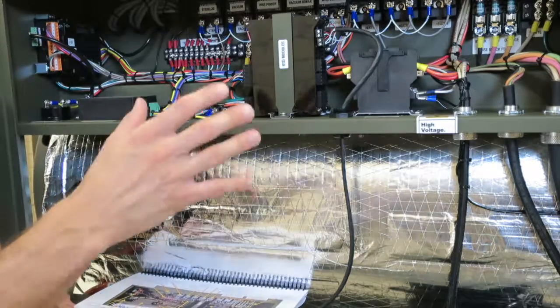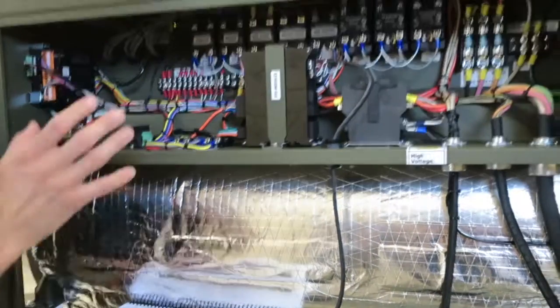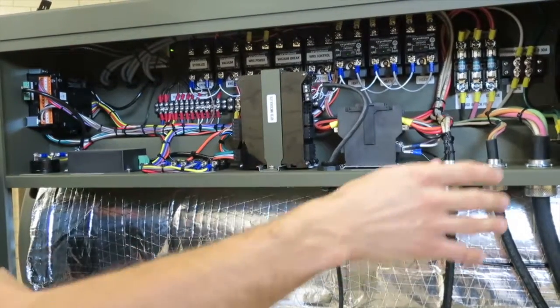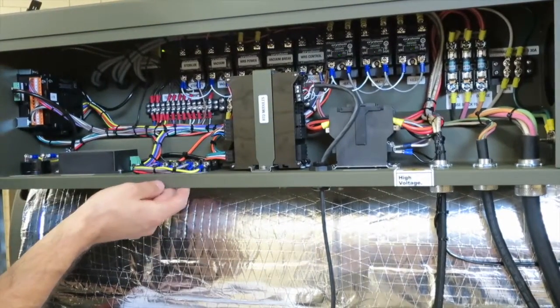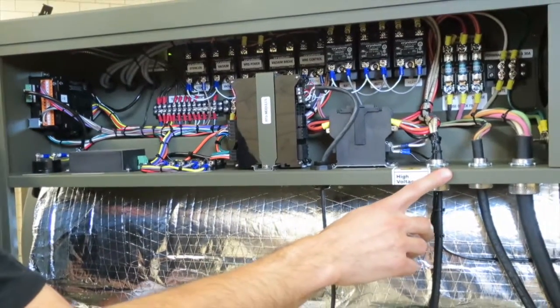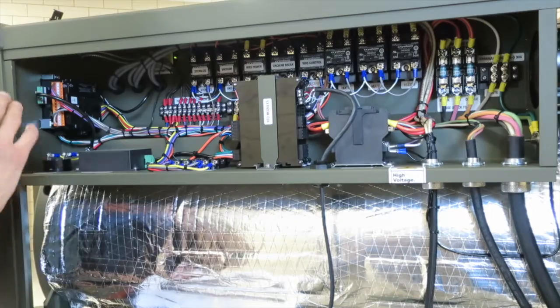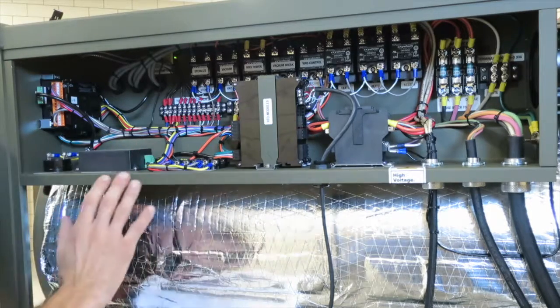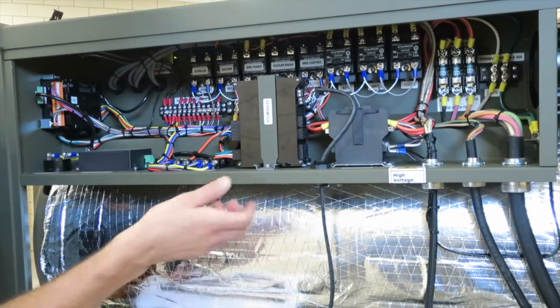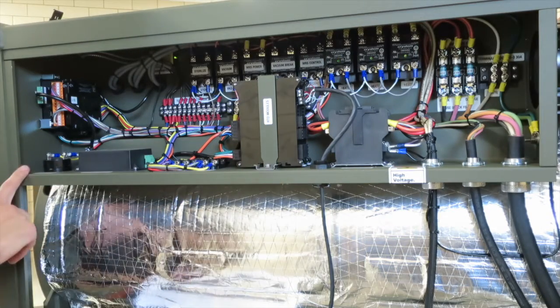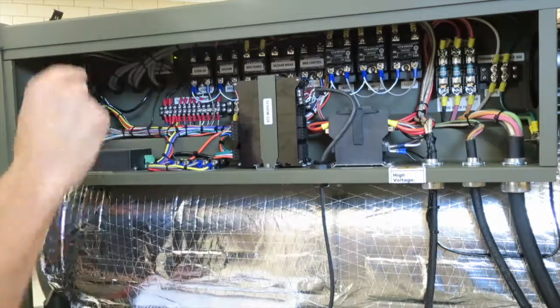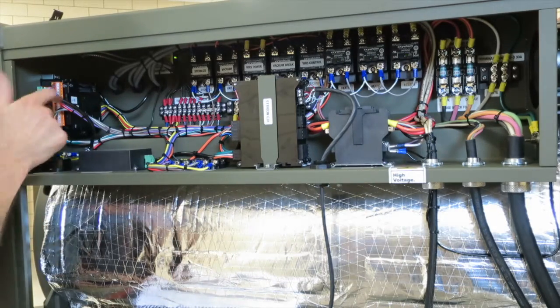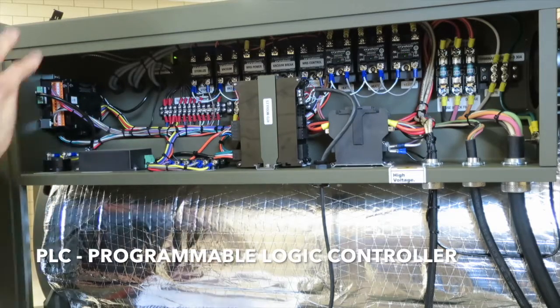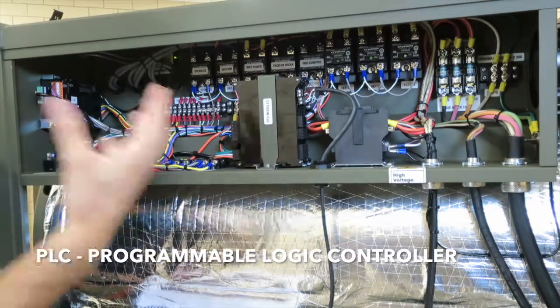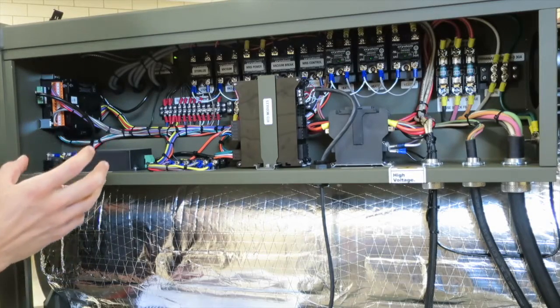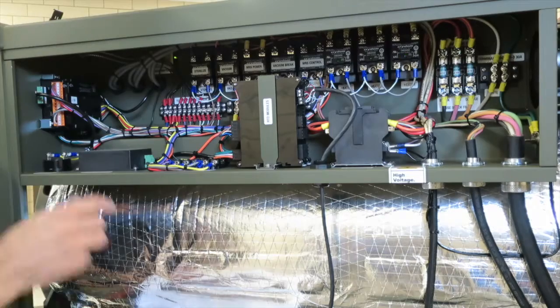Alright, now we're going to talk about the components under the right side panel. Again, this sterilizer is running, so we're going to be very careful as we point and walk through this electrical box. We do have high voltage on the right, so if you ever were performing maintenance where the sterilizer had to be on, you'd have to be very careful on this side. It would only need to be performed by trained personnel. I'm going to start from the bottom and work my way around. Right here on the left we have the PLC. This is the brains of the unit that controls all the valves, reads the temperature, reads the pressure. It's what the user interacts with on the front with the touch screen.